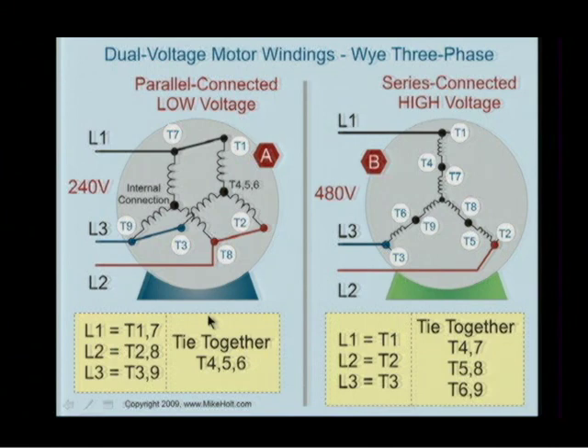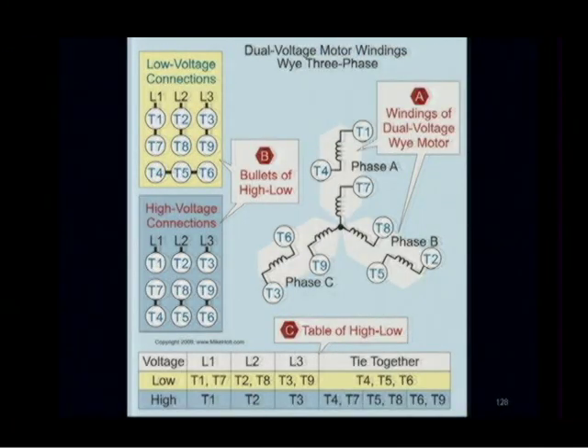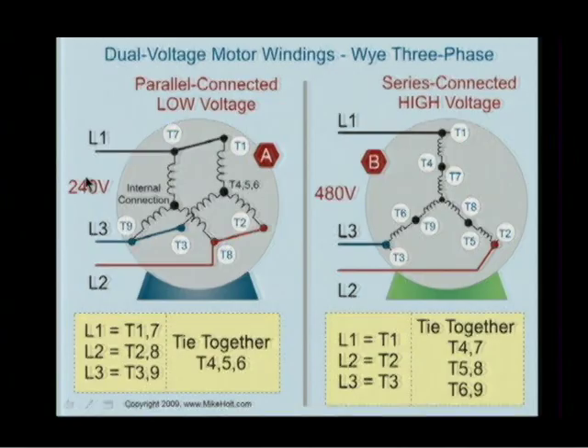Let's take a look at what this means. The voltage source would be 230. The nameplate would be 230/460, but the nominal voltage is 240/480. So don't allow that to confuse you. So we got a 240 volt source coming into a 230 volt rated motor because of voltage drop. And you have T1 and 7. Okay, 1 and 7 gets connected, as 2 and 8 get connected, and 3 and 9 get connected.